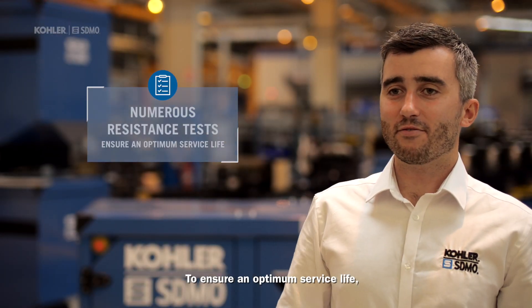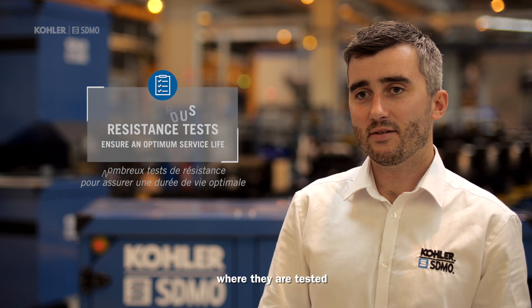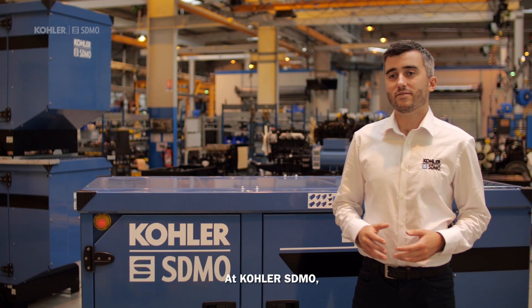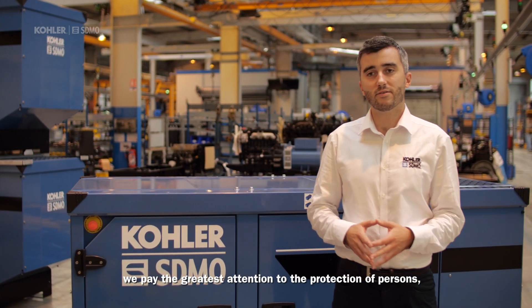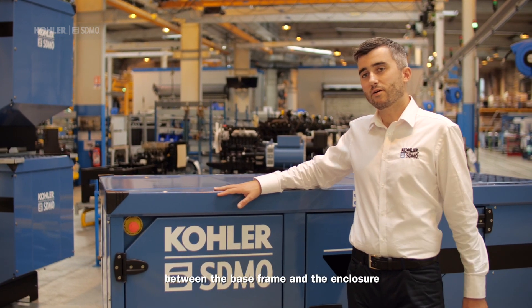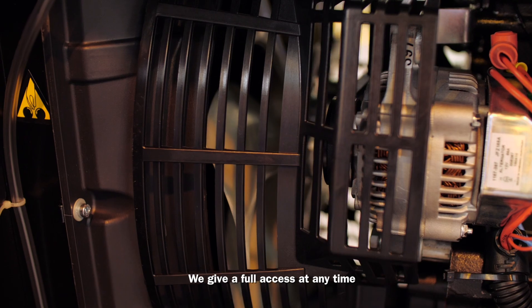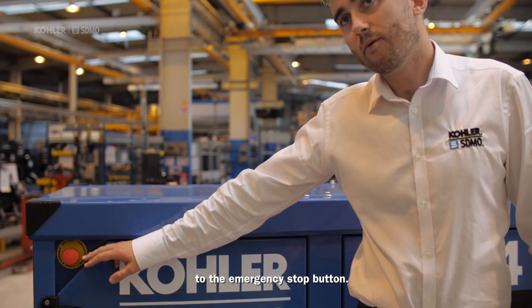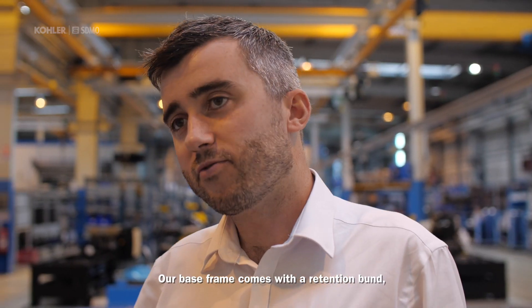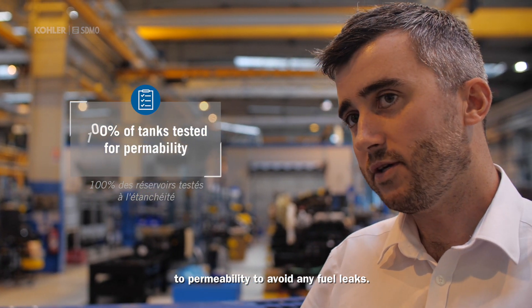To ensure an optimum service life, our base frames and enclosures are sent to the French Institute of Corrosion, where they are tested and exposed to salt spray for more than 1000 hours. At Kohler SDMO, we pay the greatest attention to the protection of persons, installation and environment. We ensure the electrical continuity between the base frame and the enclosure. Our operators are protected against hot and rotating parts. We give full access at any time to the emergency stop button, use IP64 stainless locks, and our base frame comes with a retention band. 100% of our fuel tanks are tested for permeability to avoid any fuel leaks.